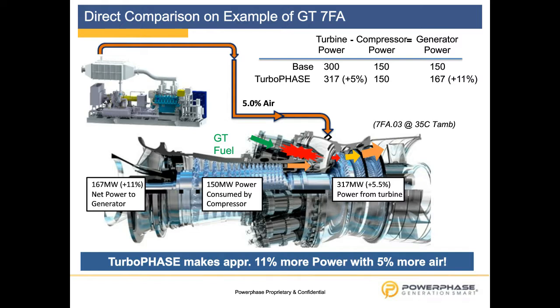Now, with our Turbophase module, we inject 5% air. That results in a 17 megawatt output increase. As we don't have any impact on the compressor side of the gas turbine, as we inject it in parallel, the output remains 17 megawatt. So if you look at the weighted average, out of 5% in mass flow, we make actually 11% more output. And that is the reason we are more efficient, simply for the fact that the compressor is using less power to compress the air. So this is why we are more efficient.